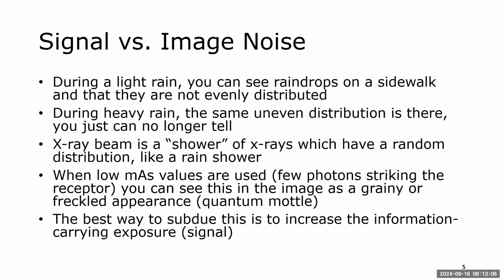Okay, but the type of noise that we're talking about here is photon starvation, or lack of enough photons to create the image.